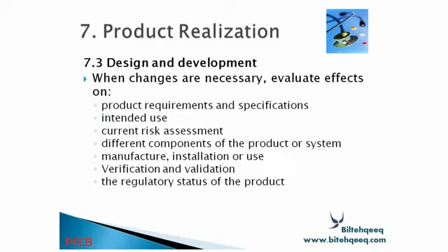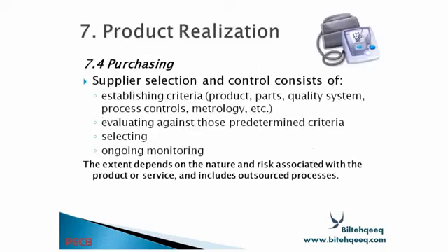If you change the design, you have to evaluate what effect it will have on product requirements and specification, intended use, current risk assessment, different components of the product or system, manufacture, installation or use, verification and validation, the regulatory status of the product. So if you are going to change the design, you have to see each and everything very thoroughly, what effect it has on the other activities.